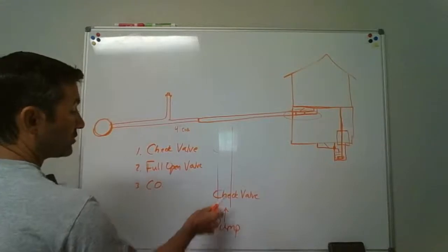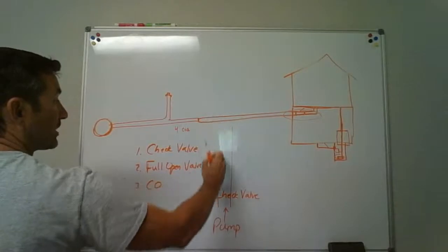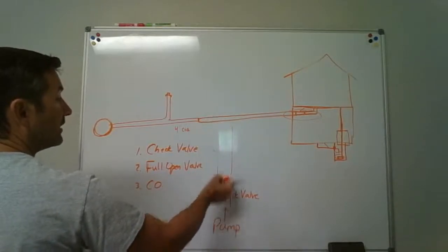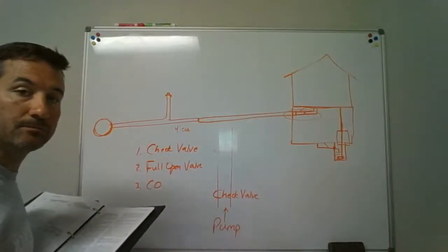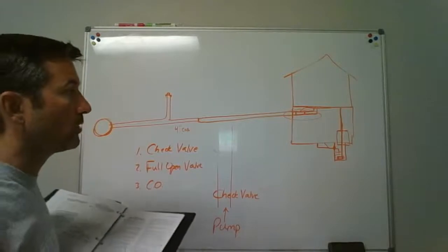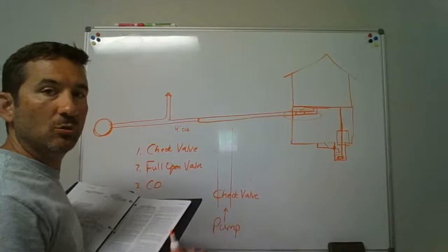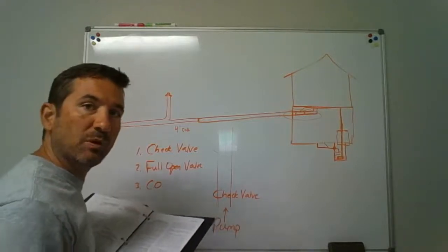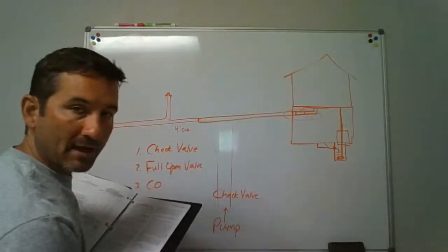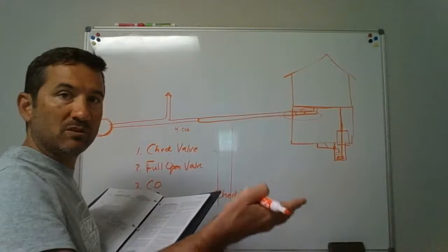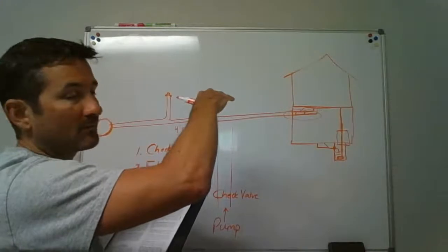installed. And so that check valve, when you pump it out, it's going to open up and let your discharge go out. But if things were going to come back, it's going to shut, close back off and not let anything fall back out of that vertical and go back into the tank. I've seen ones where the piping wasn't strapped up really well. The check valve went bad. And then what it was doing is the pump was kicking on. It was pumping it up out the line, but then it had backflow, and everything would just flow right back into the tank again, and start to fill back up the tank, and then it would say, oh, it's full. So it'd kick back on, pump it back out, and then it wasn't strapped right.